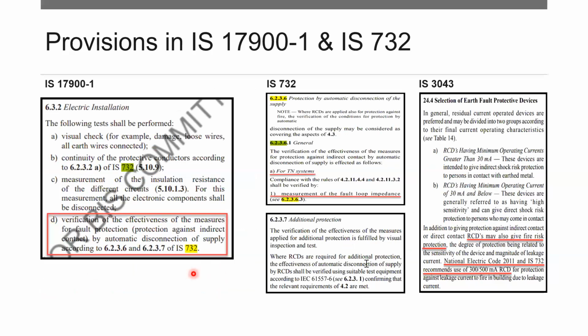Now, when we talk about the verification means, which is now part of the 17900-1 requirements, which gives a reference to the IS 732 clause 6236. Here, in case of verification for the TN systems, how do you verify the compliance? The compliance is by doing the fault loop impedance test on the site. And the additional protection can be offered by the RCDs.